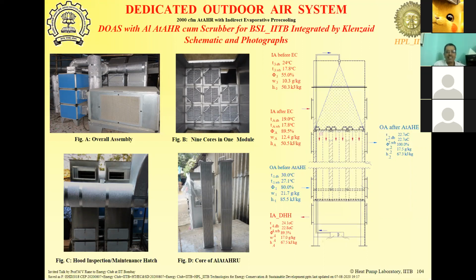Cooling. Okay. So if it is dry, then I think this slide which is up here can serve you. Can you still see the slide? Yes, sir, I can see the slide. If you take the ambient air and put it in from here, it is coming in at 30. In your case, it will probably come in at 40 or 45 degrees. The RH will be low, instead of 80%, it might be 20%, 25%. So that air will go in from here and then it will come out at maybe 25 degrees.